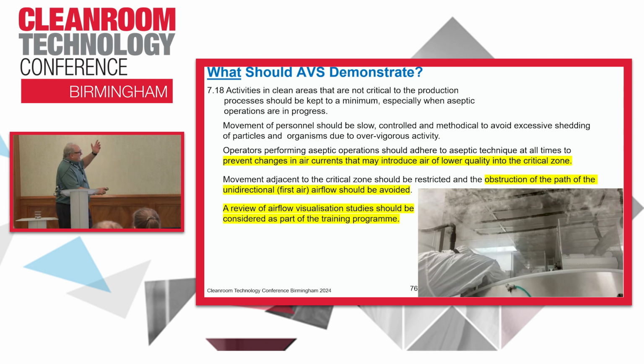So again, this is a picture, this is from a smoke study. You can see the operator's head is over the bowl, right? And smoke is obviously flowing over his head directly into where sterile components are. So this is why you want to review smoke studies and make them part of the operator training program. Can't stress that enough.